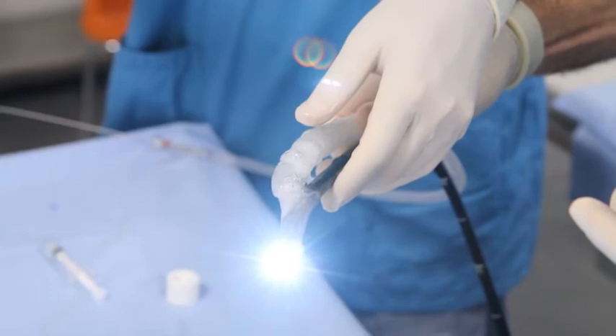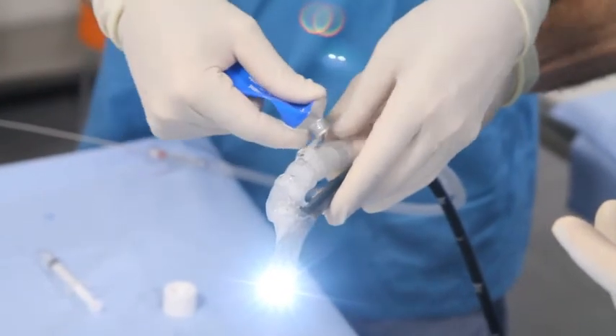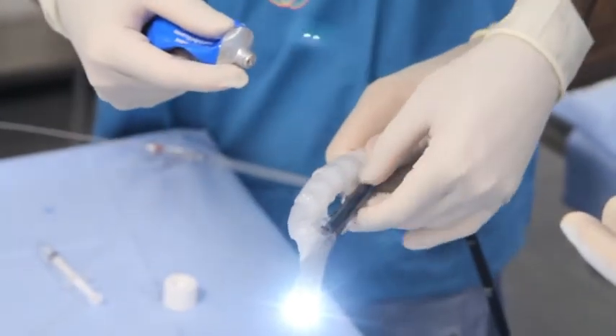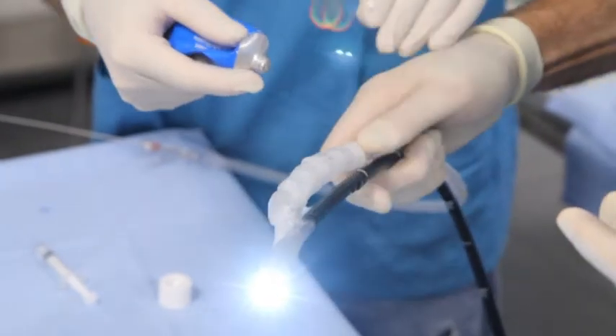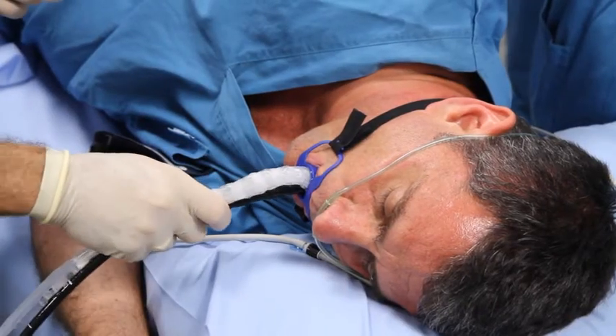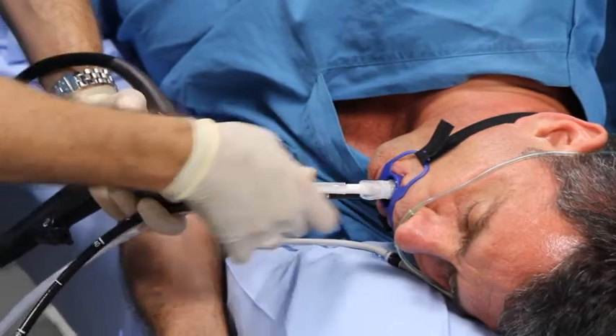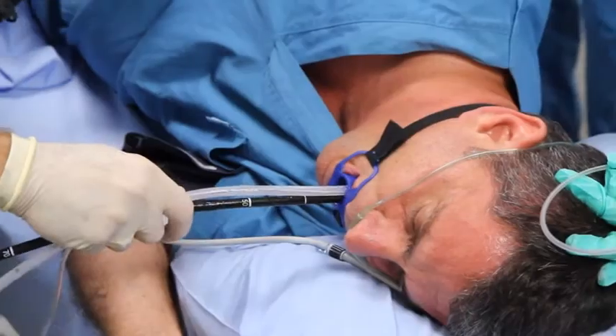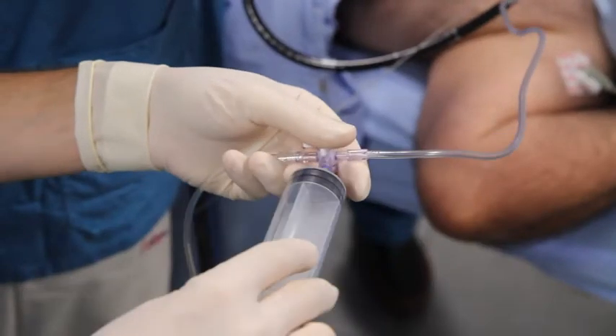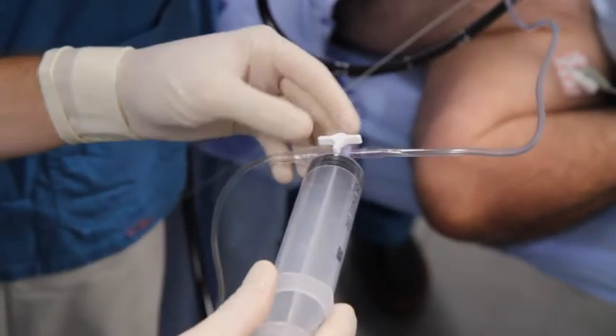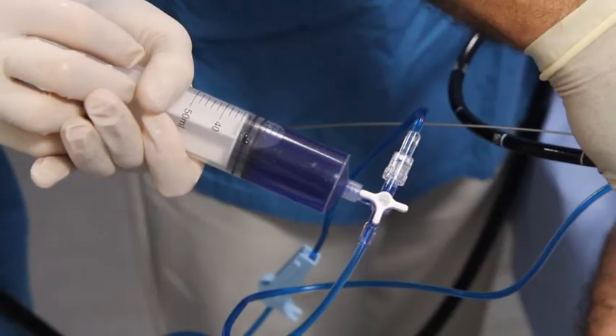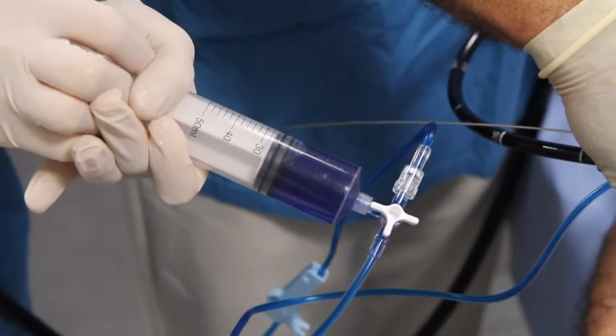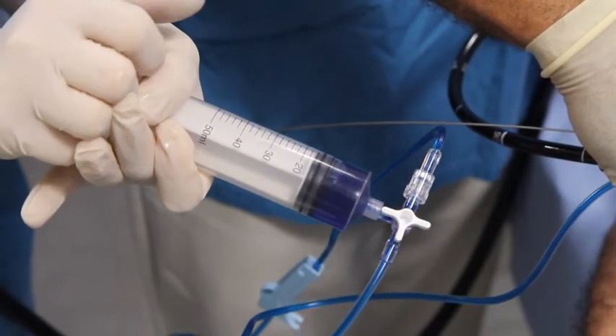Hold the endoscope and device in one hand and generously lubricate the balloon, endoscope, and valve areas. Insert the endoscope and device as you would in a normal endoscopy and pass it to the gastric antrum. Attach the 3-way stopcock to the saline bag and the syringe. Inject 30 cc of fluid to help release the balloon tip from the facilitator.